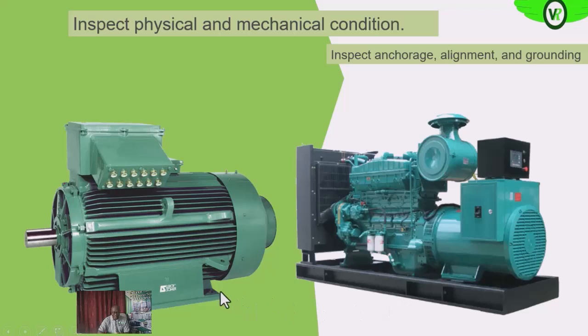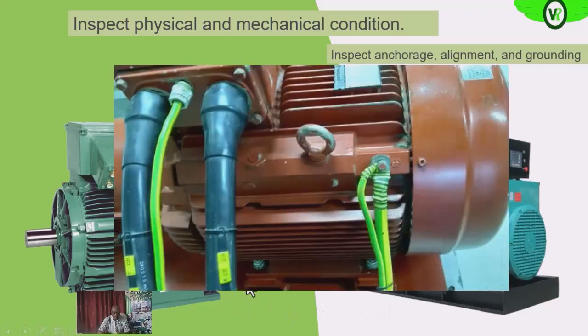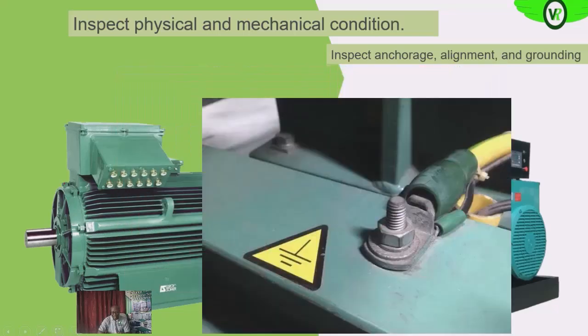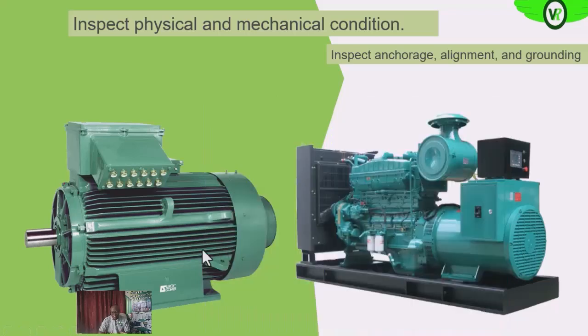Then the grounding too, if it is installed, you check to see that the grounding on each of these equipment is firmly terminated. So all of these are some of the things that you check to see that the generator or the electric motor is actually fit for use, or it can still serve its purpose properly.